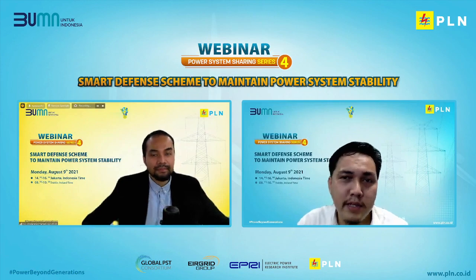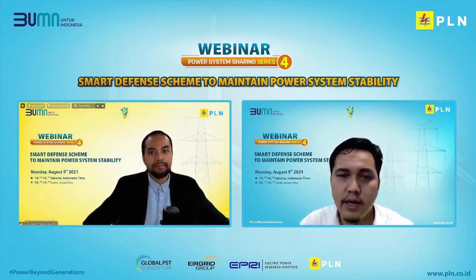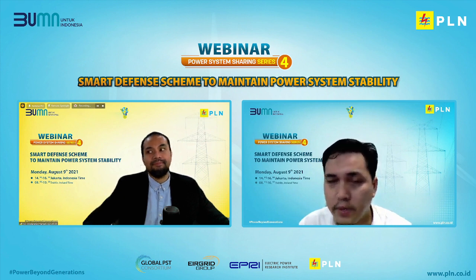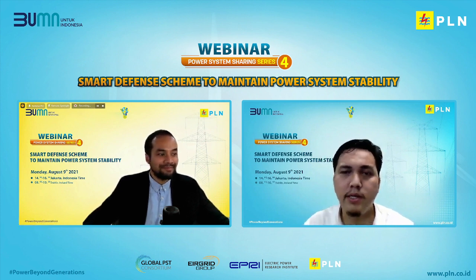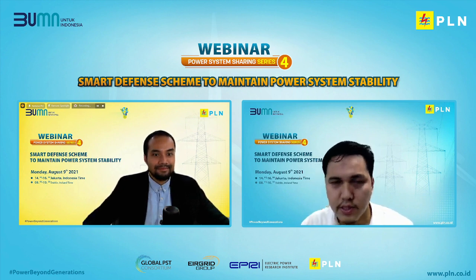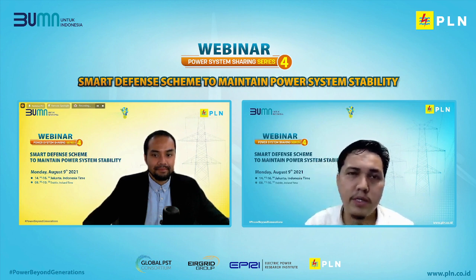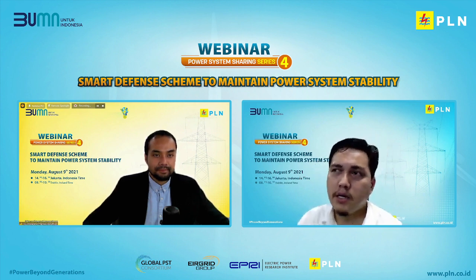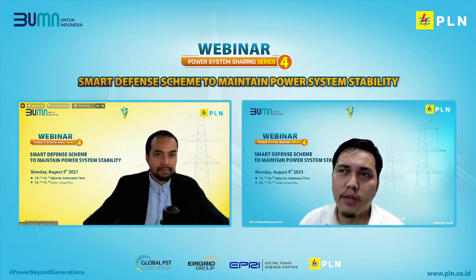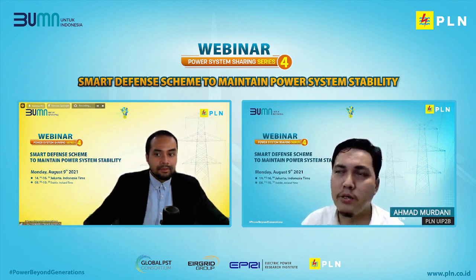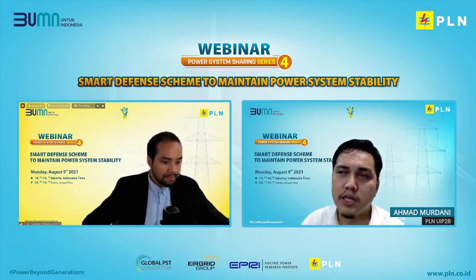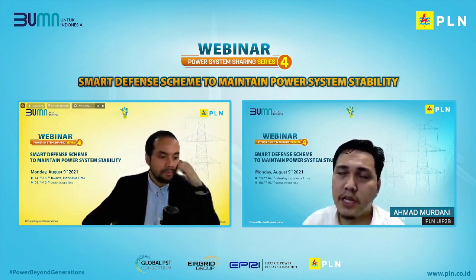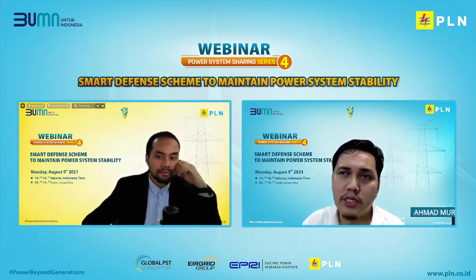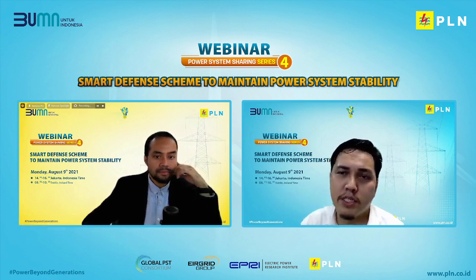My question is for Mr. Ray. I have two questions regarding the lower inertia system and also the islanding scheme that he already explained before. First, you said in your presentation that you have lower system inertia. In terms of mitigation of that phenomenon, what mitigations do you use to solve this problem? Are you pushing the existing synchronous generators to reset the rocof protection, or are you pushing the inverter-based generation to introduce synthetic inertia, and how is it enforced? This is the first question.